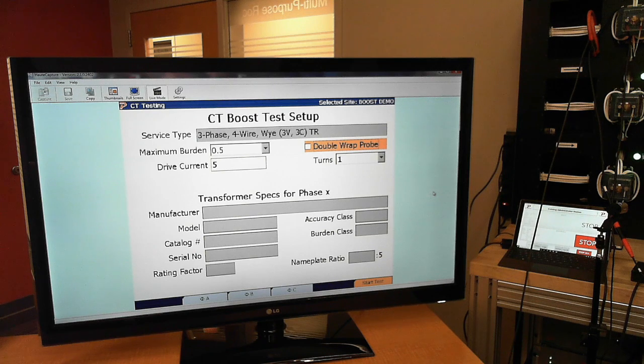At the very top right here, you just got to remember, we've got it highlighted for you if you're going to double wrap, and I've double wrapped, so we're going to have to check that double wrap box, like we always know we got to do that. I'm going to leave the burden at 0.5. I'm going to go ahead and drive 20 amps because these are 200 to 5s. So if I just drive 20 amps through there the one time, then I'm at that 10%, so I'm good. If they were 400 to 5s, I would just loop it through twice, and that would give me the 40 amps. I did only put one turn through there, but I did double wrap, so I got one turn going through. If I'd run it through more than one time, like twice for a 400, I would make that turns 2. I could make the turns 2 now if I wanted to and just run it through there on a 200 - it doesn't matter, but as long as I'm at least 10%.